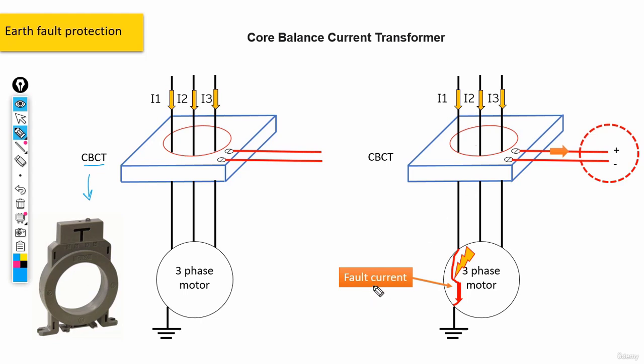When the current becomes unbalanced, more specifically, when we have a fault current in our three-phase motor, we would get a small signal, for example, here. And well, obviously, through this signal, we would understand that we are actually having this earth fault in our motor. Okay, moving on to the next slide.